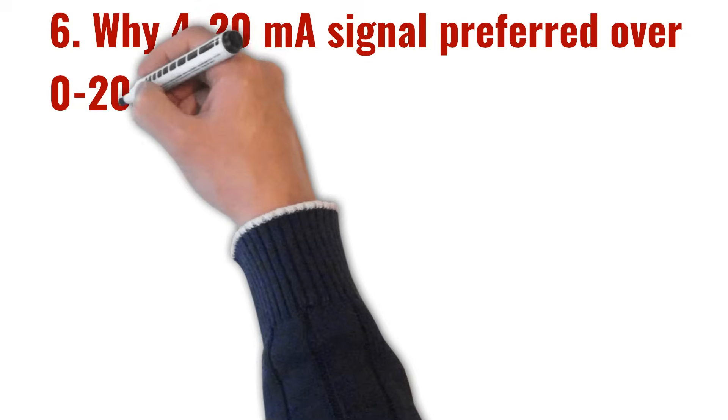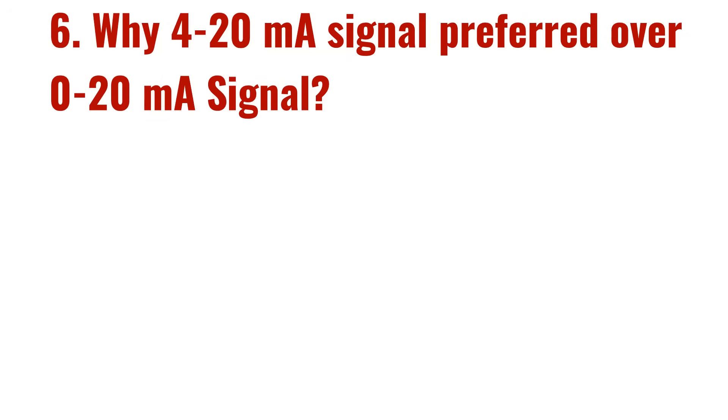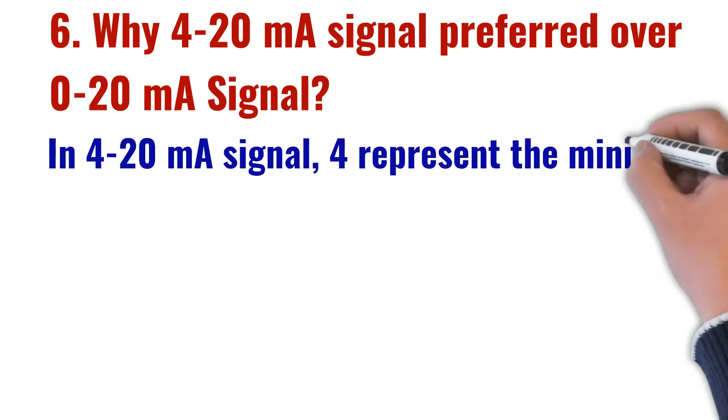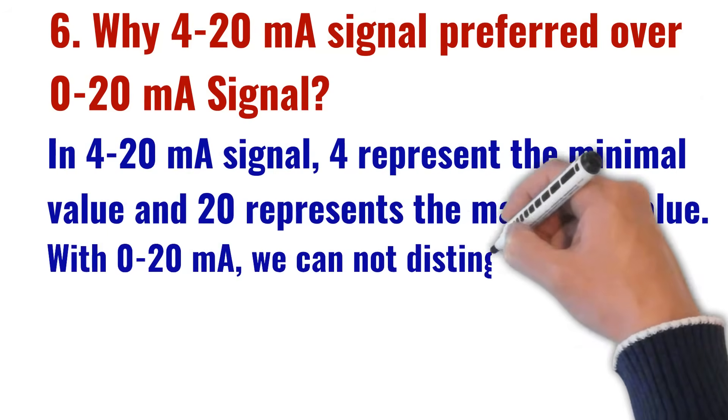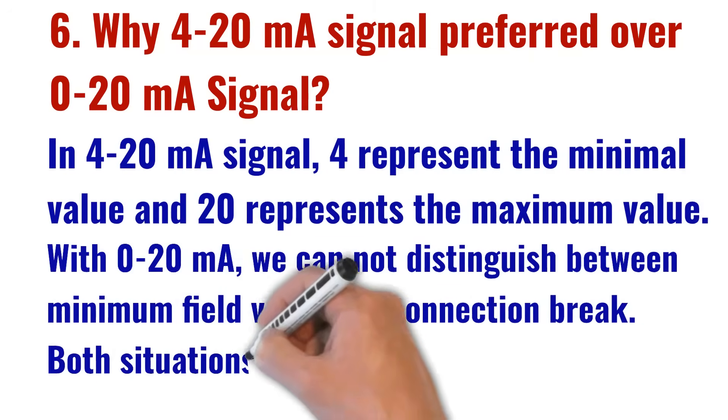The sixth most frequently asked interview question is: why is the 4-20 mA signal preferred over the 0-20 mA signal? In the 4-20 mA signal, 4 represents the minimal value and 20 represents the maximum value. With 0-20 mA, we cannot distinguish between the minimum field value and a connection break — both situations output 0 mA. In 4-20 mA, when the value is minimum, the transmitter gives 4 mA, while in a connection breakage it gives 0 mA. This way, we can easily distinguish between a minimum signal and a connection break, which is why 4-20 mA is preferred over 0-20 mA.